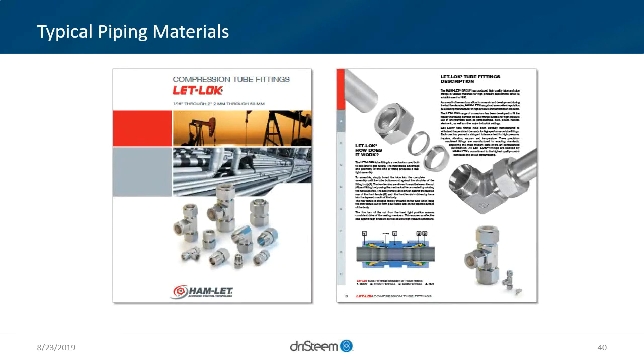Typical piping material. What the trick is, as we talk about small orifices and what DriSteem supplies and recommends for these systems, is we need to have hygiene at the top of our mind, so we're not taking oil and grease and plugging up nozzles. So what we typically use, it doesn't really matter the brand, we use Let-Lok double ferrule compression fittings for high pressure tubing, and instrument grade tubing for that cleanliness perspective. And really we want to think, how do we keep these nozzles operating and keep them operating as long as we can?